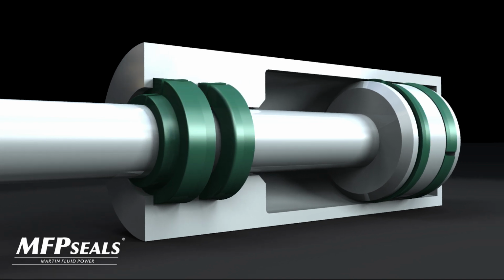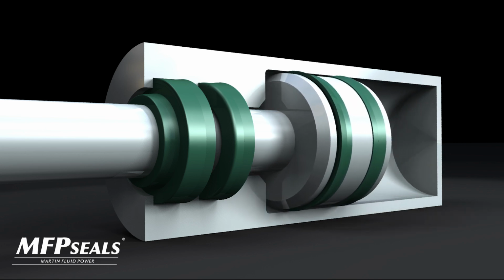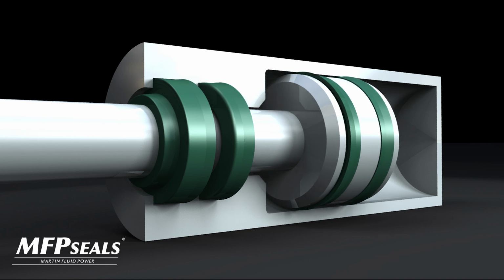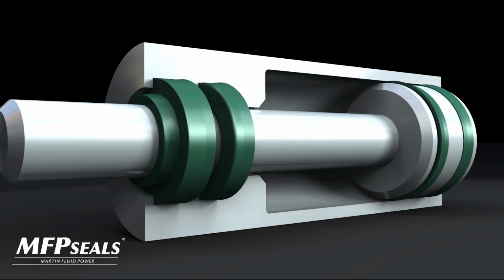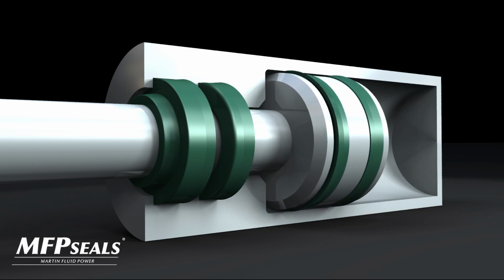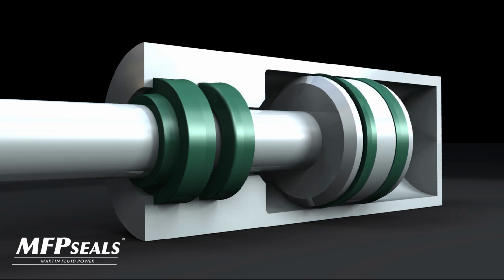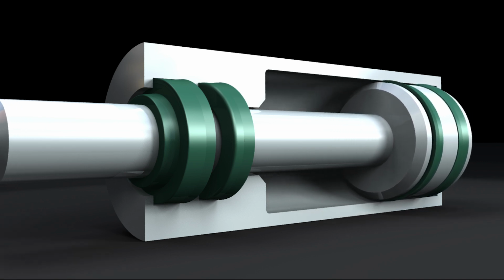Note that in this example, there are no guide rings on either the rod gland or piston. This design could result in a situation where when the seals become worn out, the piston or rod could come into direct contact with the cylinder or gland, causing damage and rendering the cylinder difficult to repair or inoperable. If you notice a reduction in performance of your pneumatic linear actuators, you should inspect it for possible seal damage, and make repairs before the cylinder or gland are impacted.